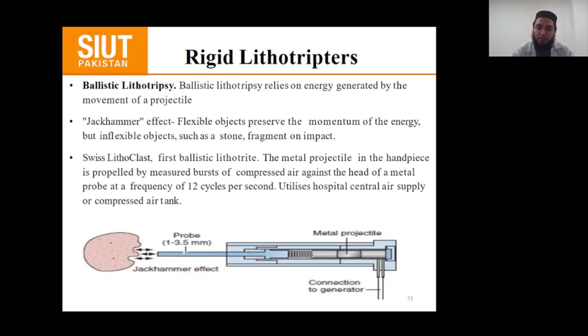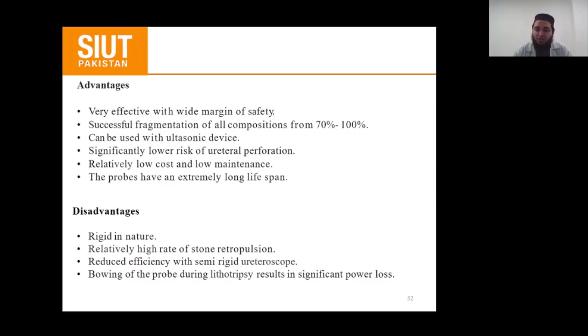Some advantages and disadvantages of ballistic lithotripsy. It is very effective with a wide margin of safety, with successful fragmentation of all compositions from 70 to 100%. It can be used with ultrasonic devices, has a significantly lower risk of ureteral perforation, and is relatively low cost and low maintenance. The probes have an extremely long lifespan. Disadvantages are that it is rigid in nature, has a relatively high rate of stone retropulsion, reduced efficiency with semi-rigid ureteroscope, and bowing of the probe during lithotripsy results in significant power loss.